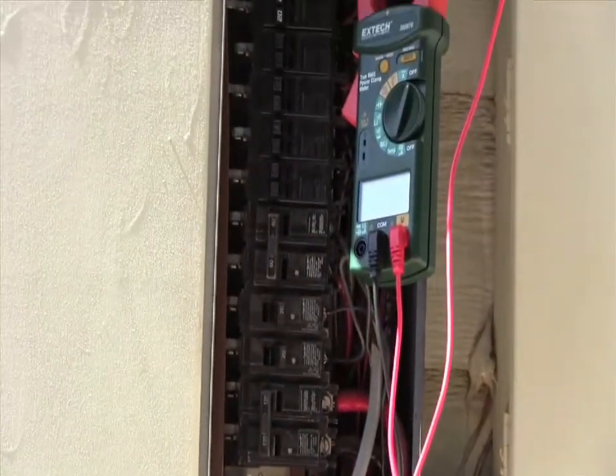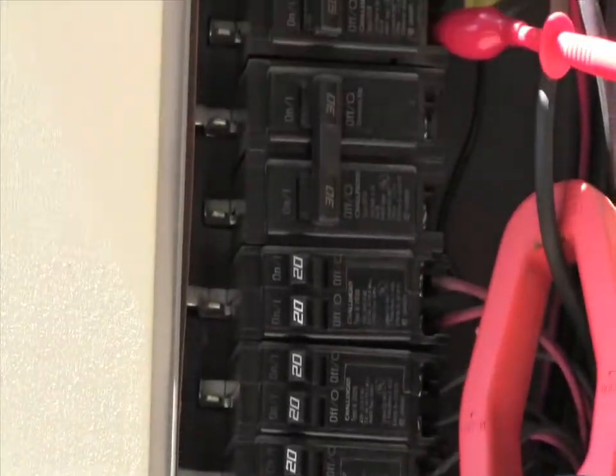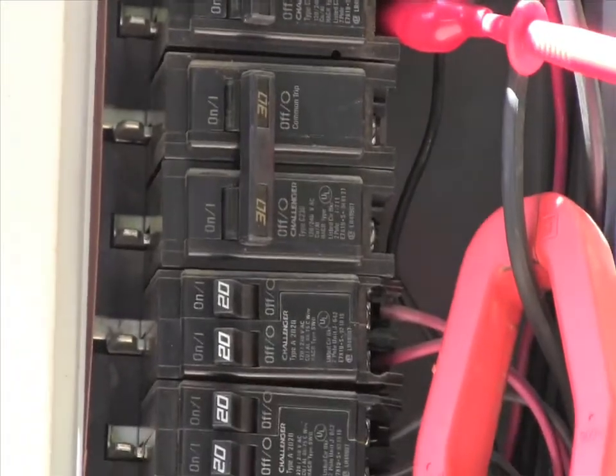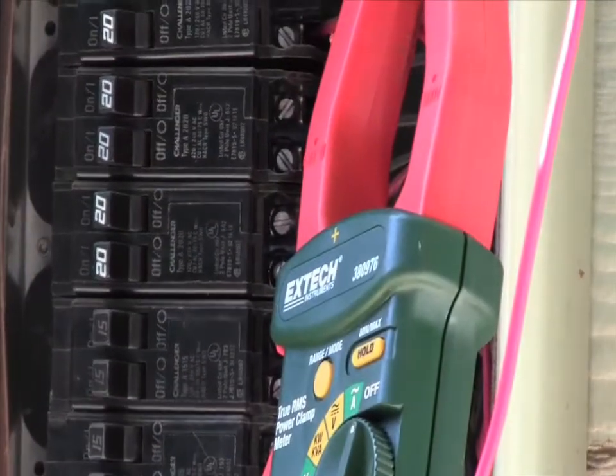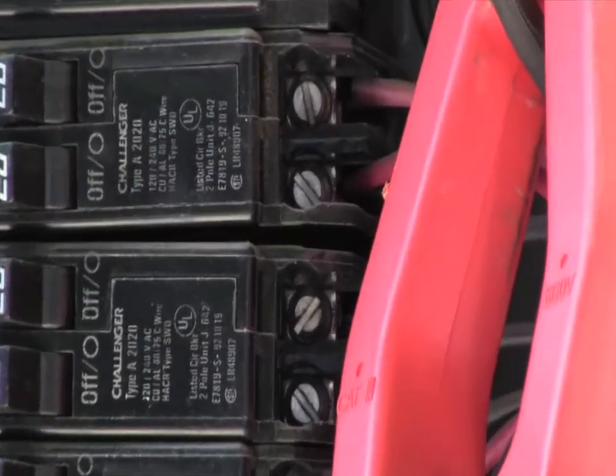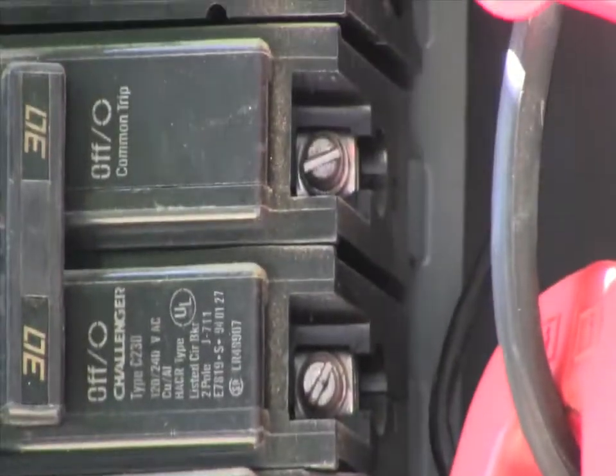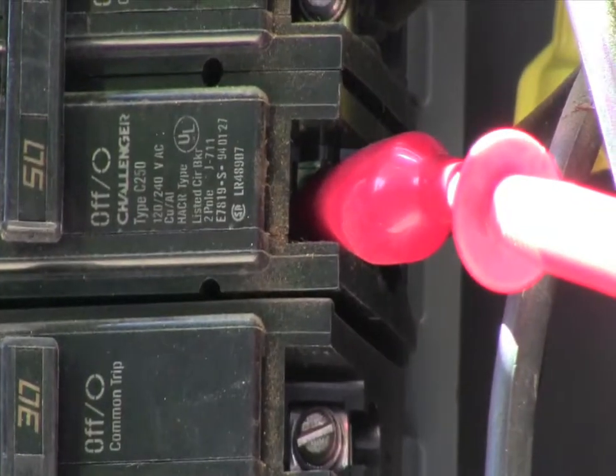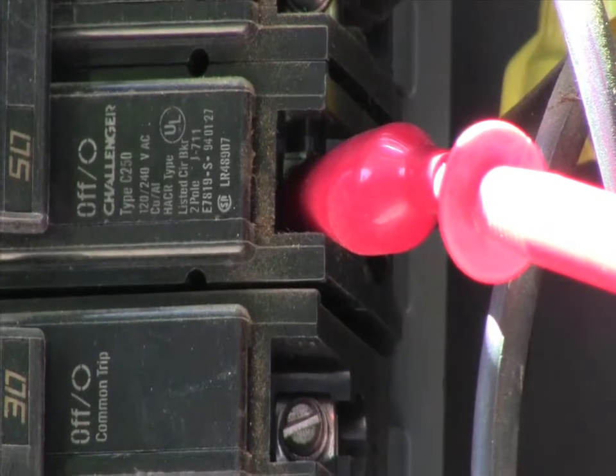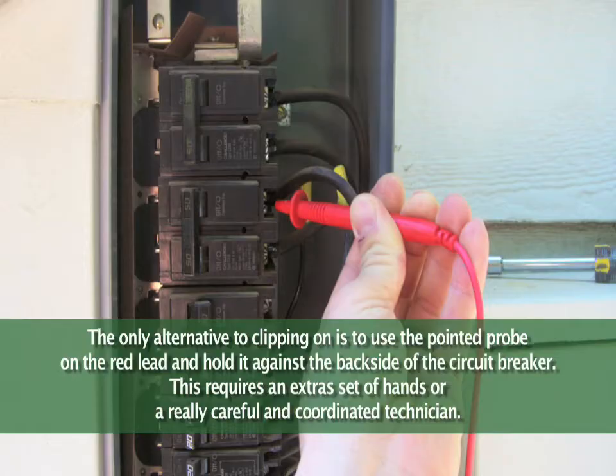And then the other thing we did up here is I clipped on to the actual nut off of the circuit breaker tie down. You see those screws right there? Well, they protrude out far enough so that I could clip on my alligator clip to leg number 1 so that I can measure the voltage through the clamp meter. The only alternative to clipping on is to use the pointed probe on the red lead and hold it against the back side of the circuit breaker. This requires an extra set of hands or a really careful and coordinated technician.